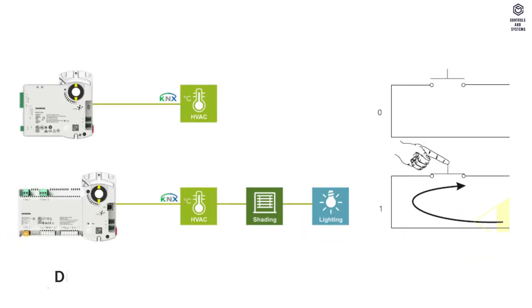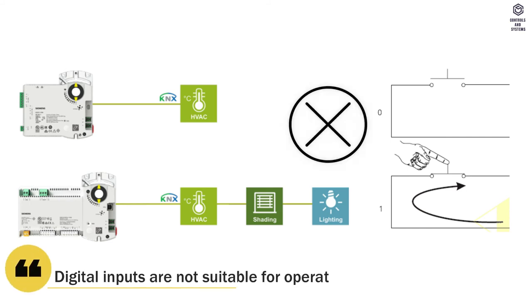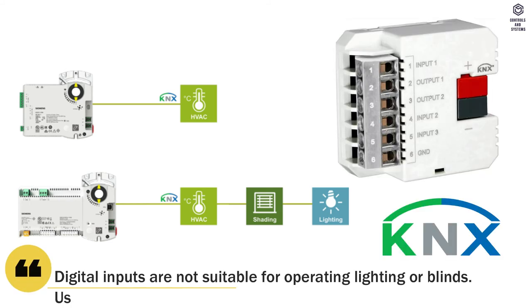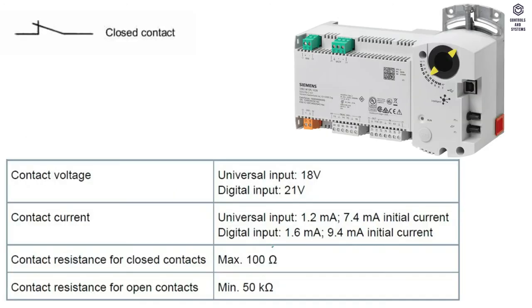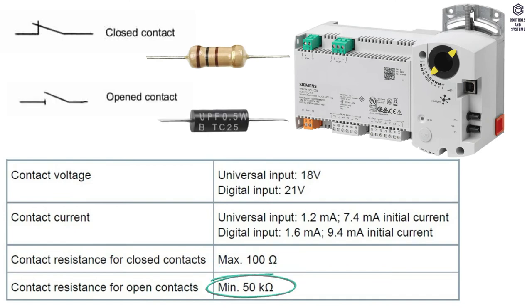Digital input: digital inputs are not suitable for operating lighting or blinds; use KNX PL link push button. Contact resistance for closed contacts is maximum 100 ohms. Open contacts is minimum 50 kilo-ohms. Contact query voltage and current range are shown in the table.